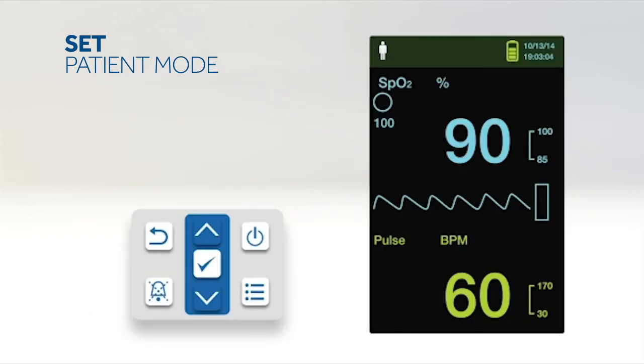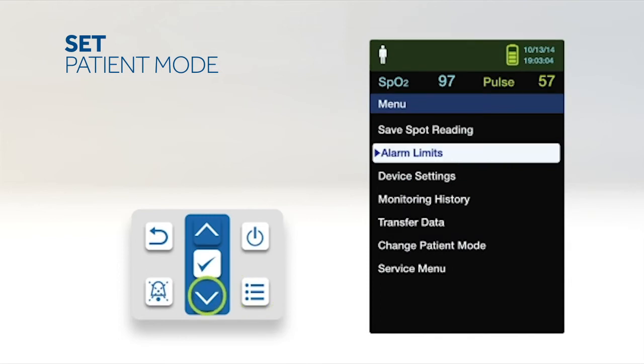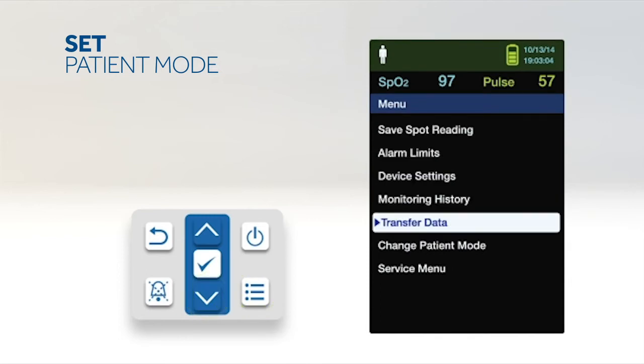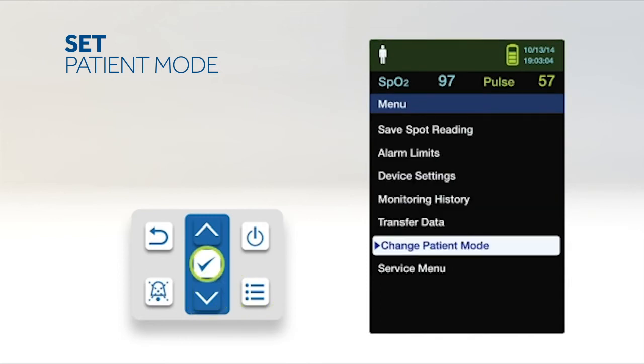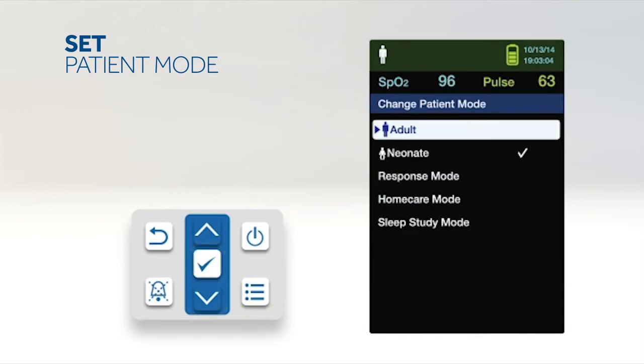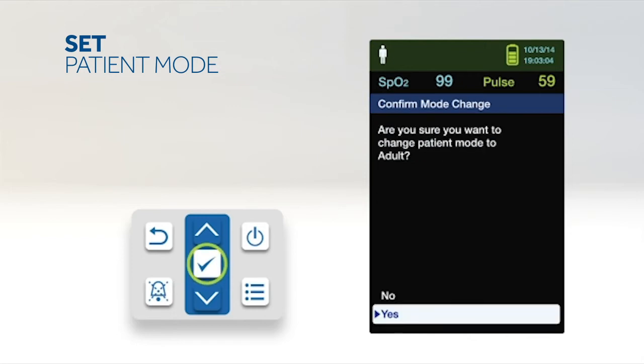The patient mode can be set to either adult or neonate. To select the patient mode, press the menu button. Scroll to change patient mode and press the OK button. Select the appropriate patient mode. Press the OK button to confirm.